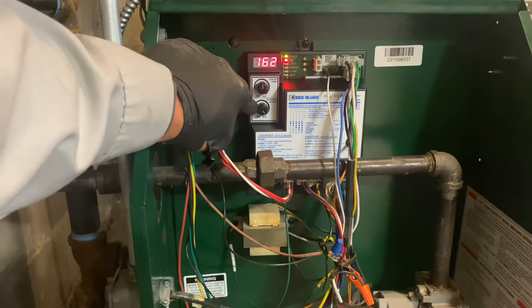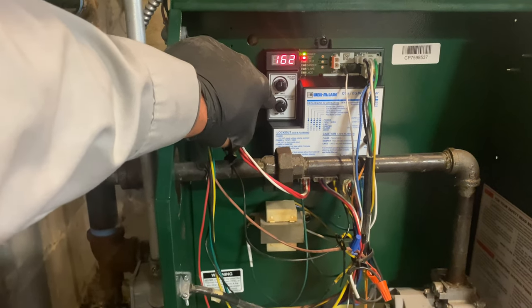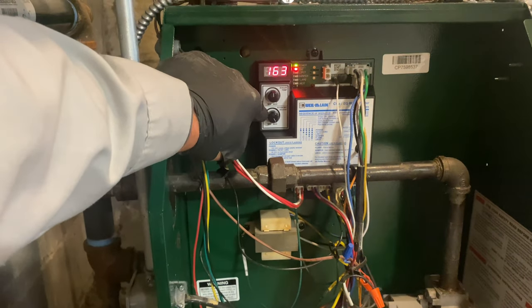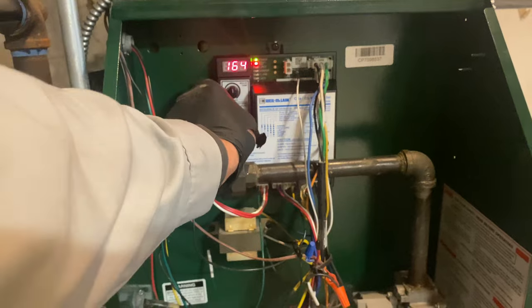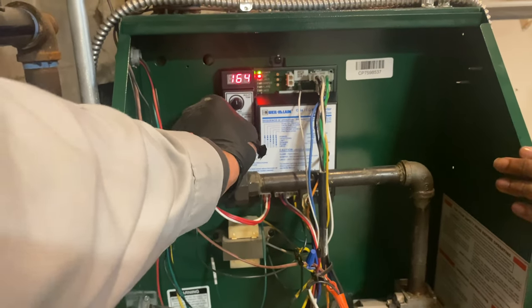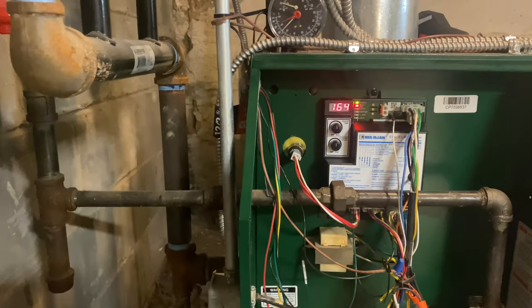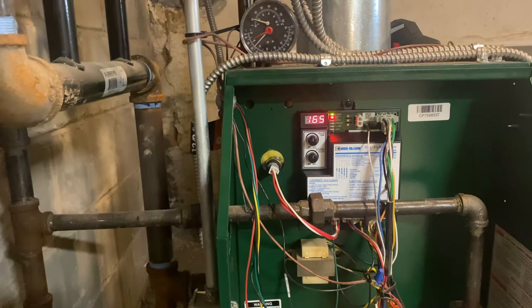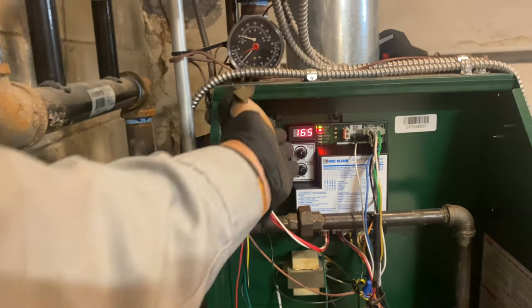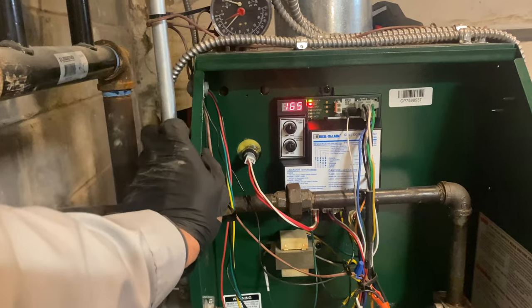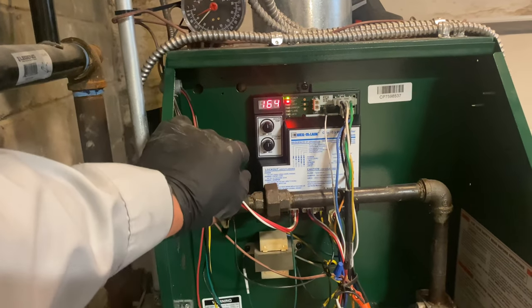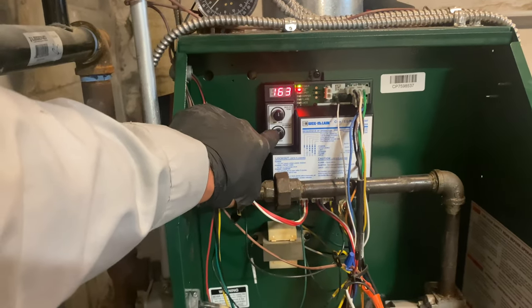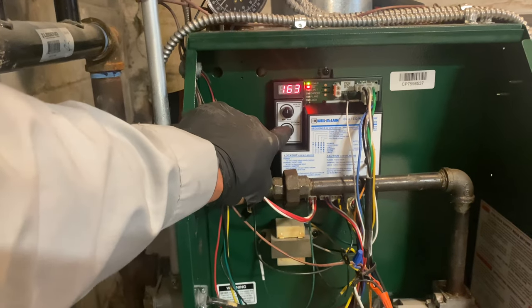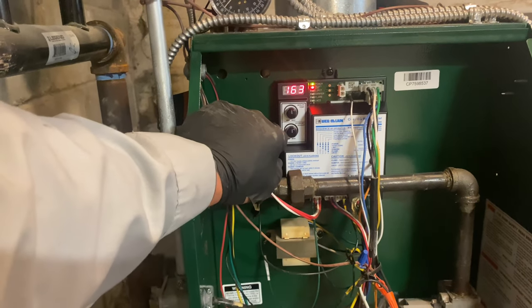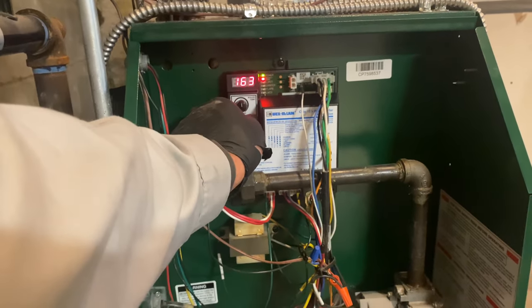The economy adjust is for gaining efficiency. It will limit the amount of time, the runtime of the circulator before a call for heat. For example, the boiler is at around 165 degrees - that's what it thinks it is right now, 164, it's moving around. By adjusting this, it will adjust the runtime of the circulator before it fires up.